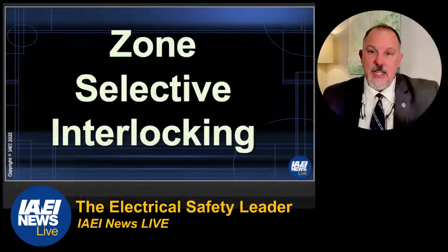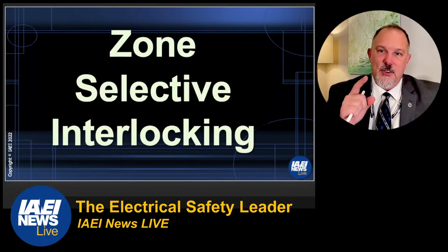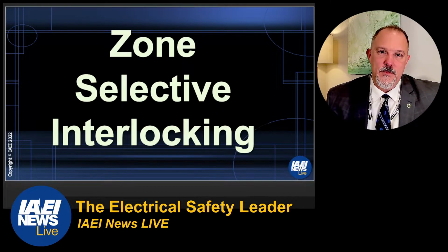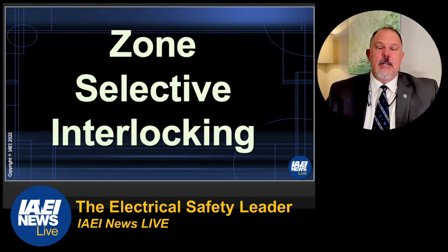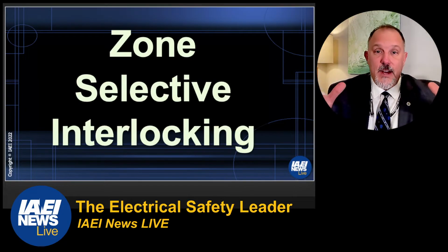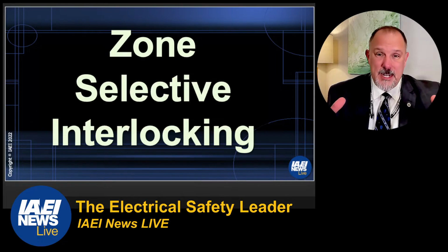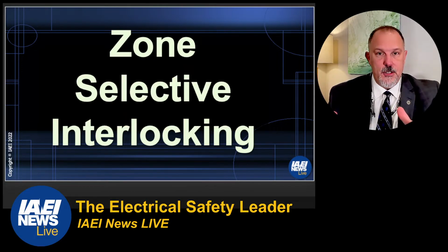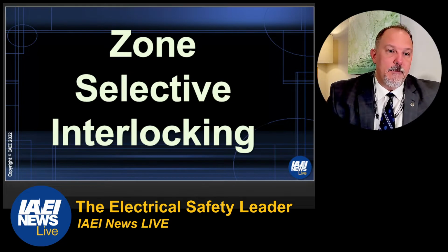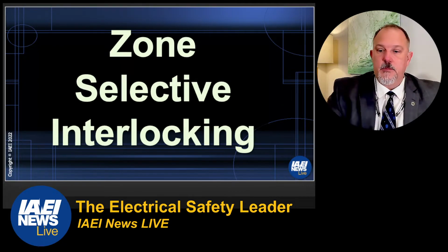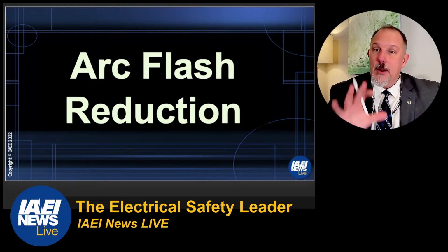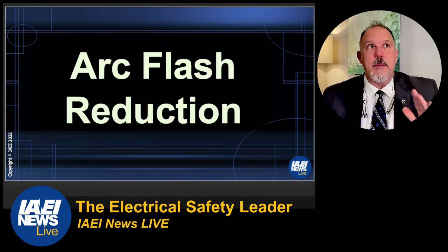And I'll tell you, at the heart of ZSI, meaning the first letter of each of these words, is equipment protection. The goal of zone selective interlocking is to provide equipment protection, reduce the damage in the equipment within which this technology is employed.